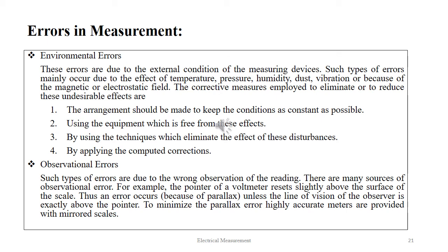Environmental errors are due to external conditions of the measuring devices, mainly occurring due to the effects of temperature, pressure, humidity, dust, vibration or magnetic and electrostatic fields. The corrective measures employed to eliminate or reduce these effects are: keeping the environment or conditions as constant as possible, using equipment that is free from these effects, using techniques that eliminate the effect of these disturbances, and applying computed corrections.